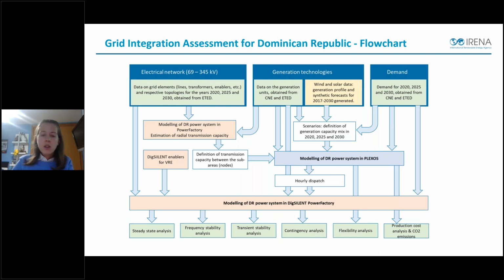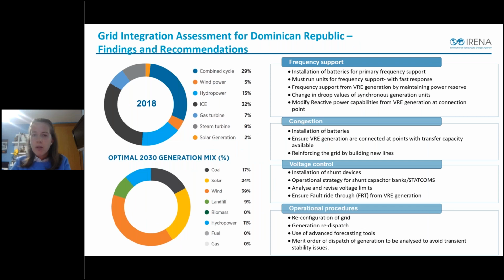The study considered different shares of VRE, starting with 7% in 2020, following the Dominican Republic target of 25% in 2025, up to 45% in 2030. The power system was created in DIgSILENT PowerFactory, and different technical studies were conducted as said before. Different contingencies and faults were simulated for the different sub-scenarios selected for study and a critical snapshot of the system. Critical snapshots were chosen based on VRE generation, demand, power of largest generator, inertia in the system, and spinning reserve. Next slide, please.